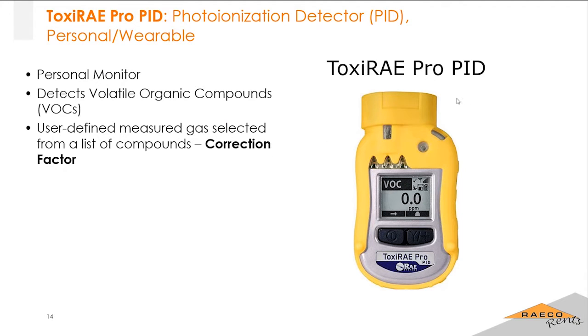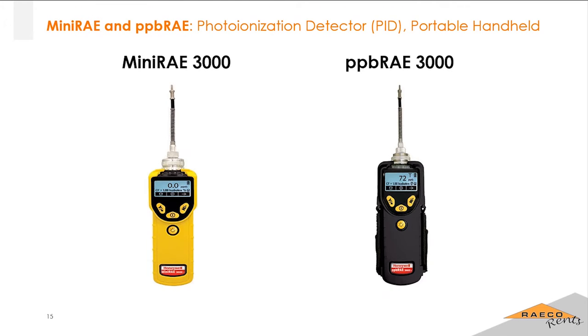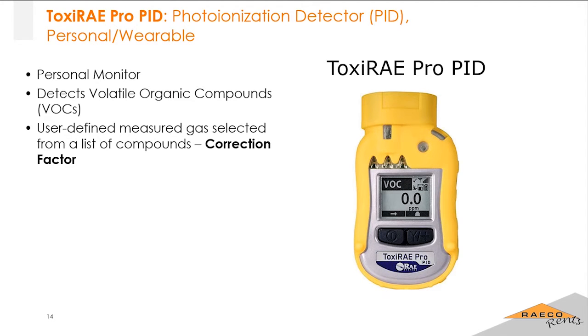For the ToxiRAE Pro, there's also a different instrument, the ToxiRAE Pro PID, your personal wearable PID monitor. Like anything else, it detects VOCs, and you can select a correction factor from a list of compounds. So if you know you're measuring propanol or something like that, you can select that correction factor and it will respond with the correct correction factor for propanol. Very important to note that a PID is not specific, it will respond to any volatile organic compound.